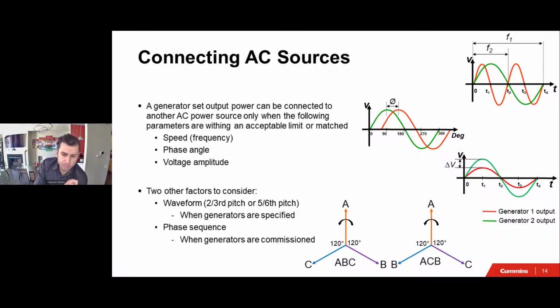So the three things that we always need to check when we're connecting two AC sources: we need to make sure that the frequency, or the speed, between those two sources is matched, or within 1/10 of a hertz, for example. The phase angle difference between the two must also be kept to a minimum, say plus minus 10 degrees or plus minus 8 degrees or so.